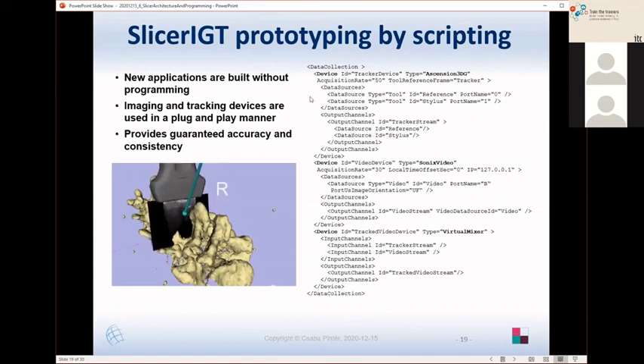So for example, in this file, you say that you have an Ascension 3D tracker, you have two tools, a reference and a stylus. You say that your ultrasound is a Sonix. The ultrasound image orientation is UF. You have some IP addresses, etc. And then you say that, okay, I want to mix these two devices into the same mixed device that contains not just the tracking, but also the image together, so that they form a whole information bundle that can be used in Slicer.